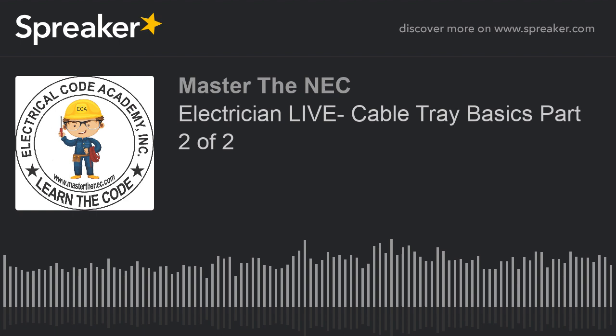If I install them in accordance with 392.22(A), I follow those rules, I put these multi-conductor cables in there. If I don't have more than 3 current-carrying conductors in that individual cable assembly, then guess what? I don't have to do any adjustment. I'm perfectly fine. And it's also reminding me that I'm not going to take all of the conductors in that cable tray and act like they're being bundled, and then apply something in 310.15(B)(3). I don't have to do that.